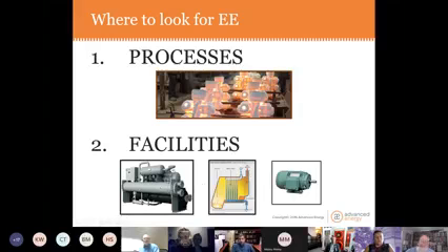Most manufacturing plants, easily 50 to 60% of their electricity is consumed by motors, turning something: turning a pump, turning a fan, turning a compressor on a chiller, turning a blower motor on an aeration basin in a wastewater treatment plant. Motors are everywhere in manufacturing plants, and big ones, 100, 200, 300, 400 horsepower. They consume a lot of electricity. So really focusing on these two areas, you can figure out where to get some energy efficiency.